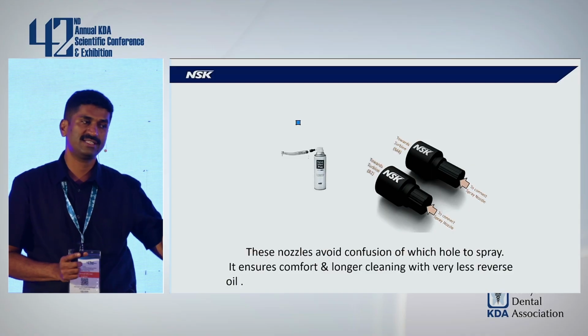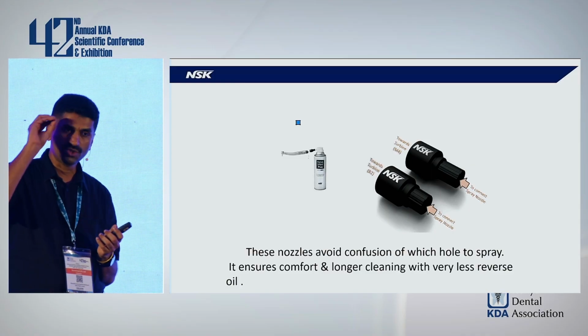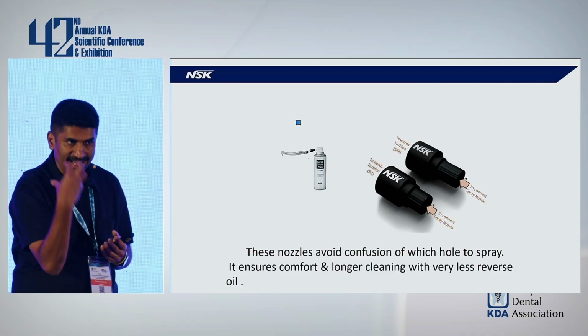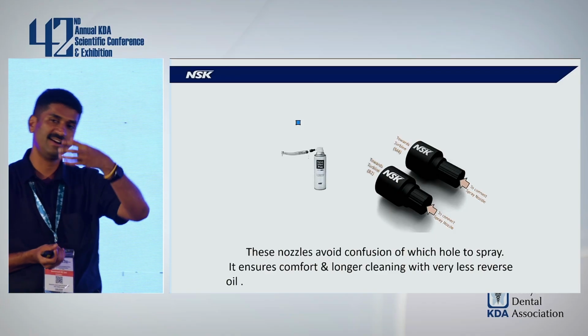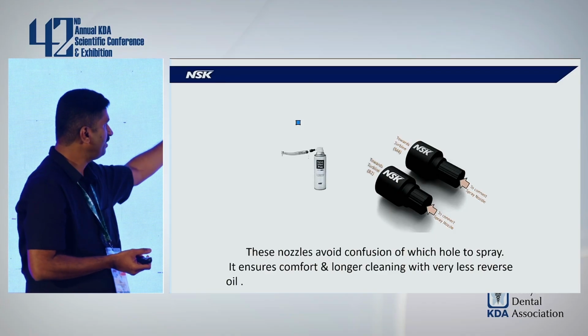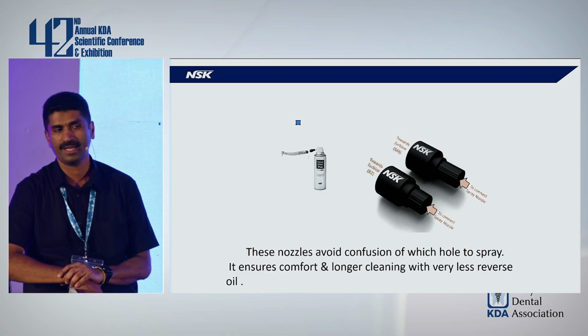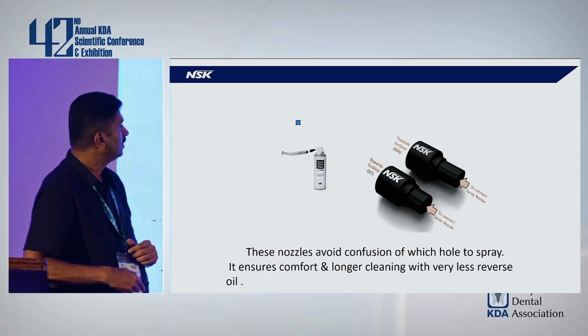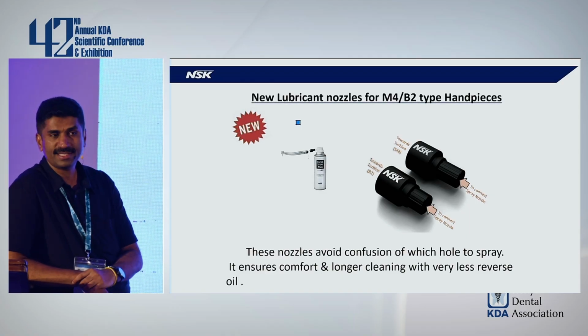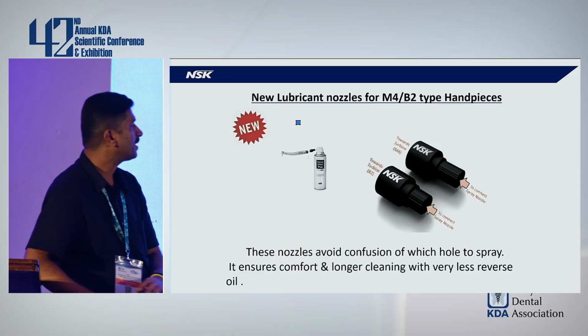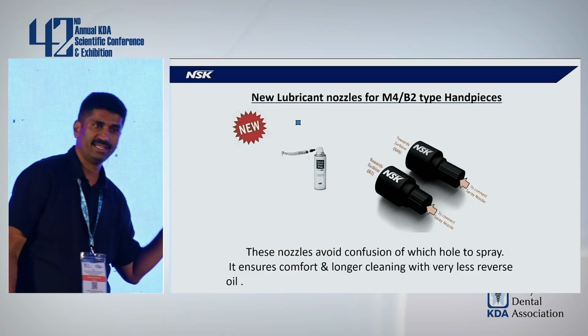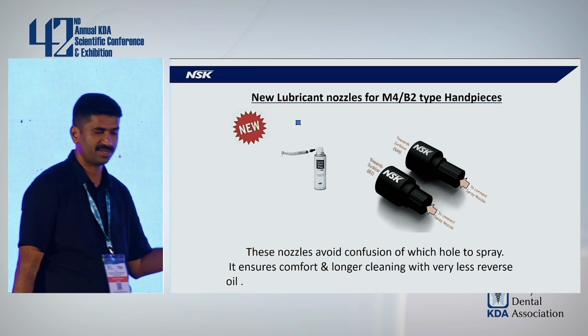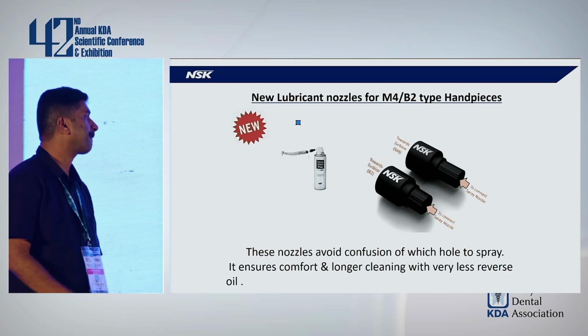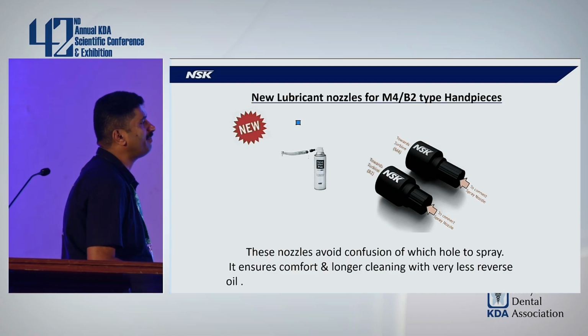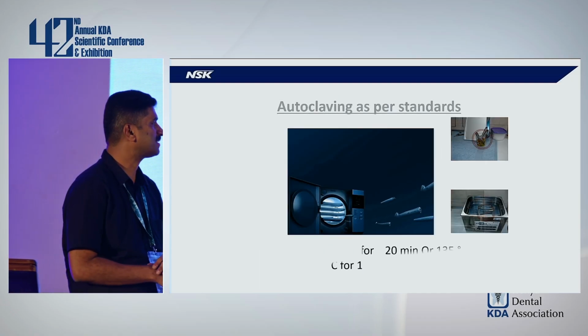And this adapter ensures that the oil goes to the proper hole and the proper lubrication takes place, and 100% of oil comes out from the head without any leakage in between. So this will ensure that proper lubrication of the handpieces is done. Okay? So this is something new, only available with NSK. Of course, it's compatible with all types of handpieces, not only NSK, but these adapters are available only with NSK. So this is regarding the proper way of lubrication of the handpieces.